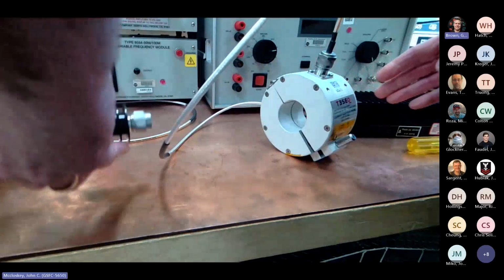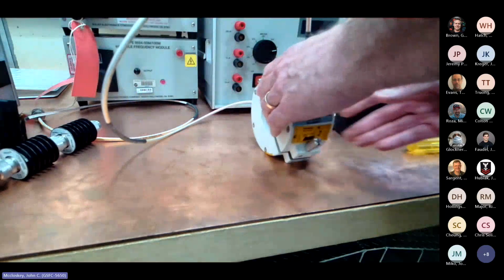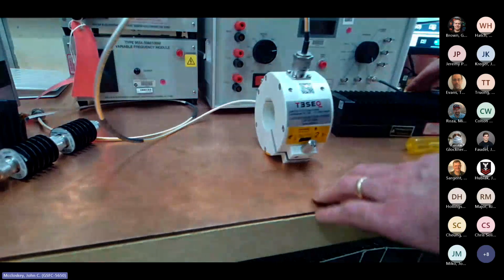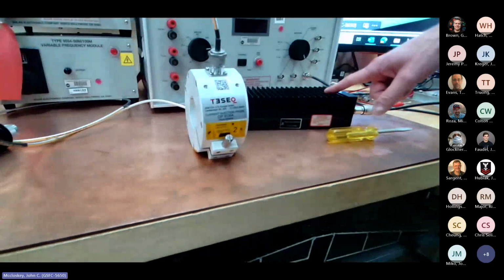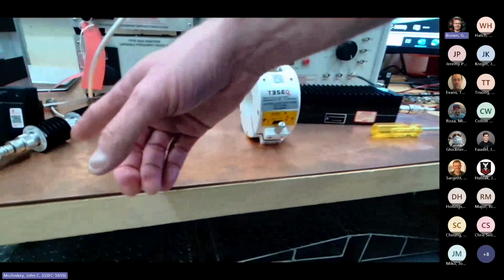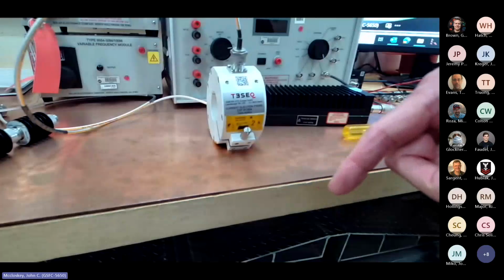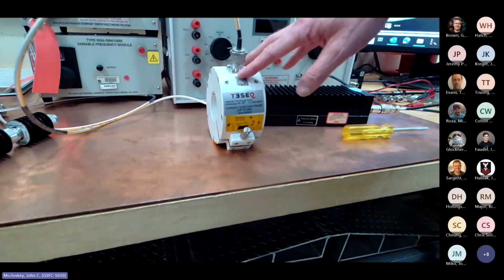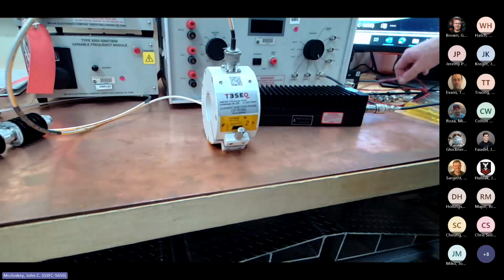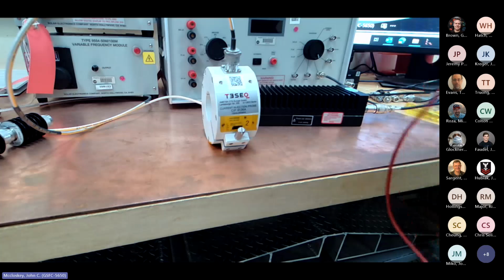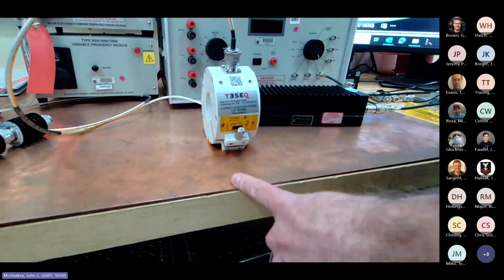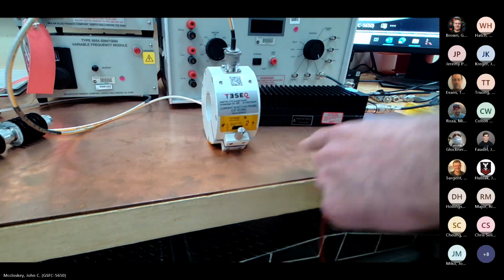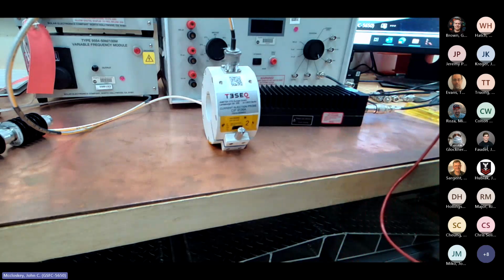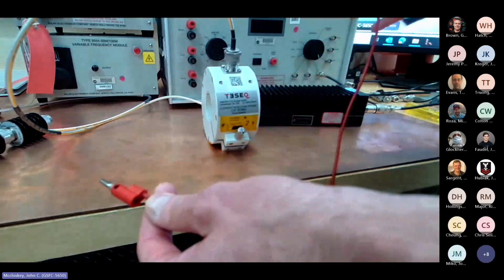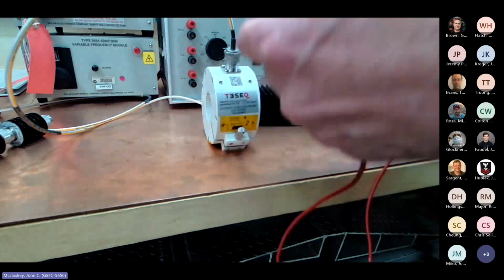When you're injecting into the cable under test, you want to keep the drive configuration. So if you used the attenuator for the calibration, you leave it in. You can adjust the attenuation on the monitor side as needed, but the drive circuit up to the probe should be the same. The lowest impedance you can inject into - if you're injecting into a shielded cable with the shield terminated to chassis at both ends, it's basically going to be a short circuit, at least at low frequencies. Then your loop inductance kicks in at higher frequencies. So generally, for demonstrating purposes, I just take a piece of wire and short the ends together.